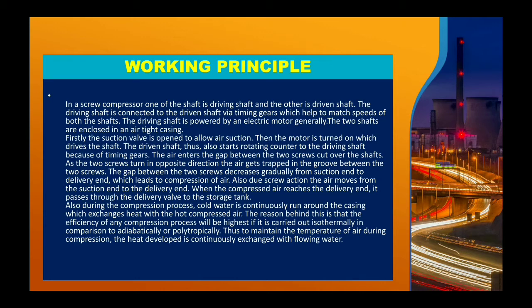When the compressed air reaches the delivery end, it passes through the delivery valve to the storage tank, where it is stored. By using the valve on the storage tank we can use the compressed air at a certain pressure. A pressure gauge is provided in the storage tank to measure the pressure of the compressed air. During the compression process, cold water is continuously run around the casing, which exchanges heat with the hot compressed air — this is an isothermal process, which increases the efficiency of the system compared to an adiabatic process.